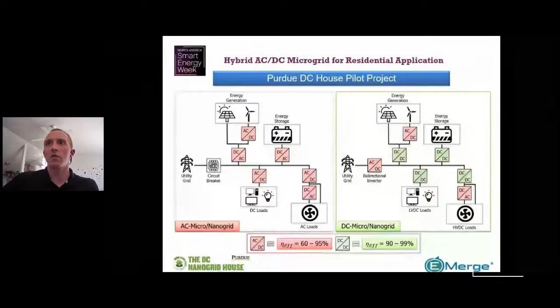Our nanogrid is composed of several pieces of equipment. We have a bidirectional inverter at the front with isolation transformers on input and output. We have a DC-DC converter module connected to our solar panels—a 14.3 kilowatt installation on the house's roof. The DC-DC converter also has maximum power point tracking built in, and it helps regulate our 380 volt DC bus, which constitutes the backbone of our nanogrid.